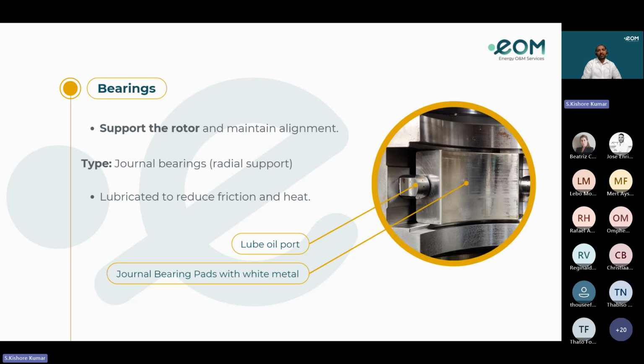In steam turbines, they do not use rolling elements like balls or rollers, but instead rely on a film of lubricating oil to separate the shaft from the bearing surface. Here we can see the journal bearings. They support the rotor and give radial support to the rotor, and they are lubricated to reduce friction and heat.